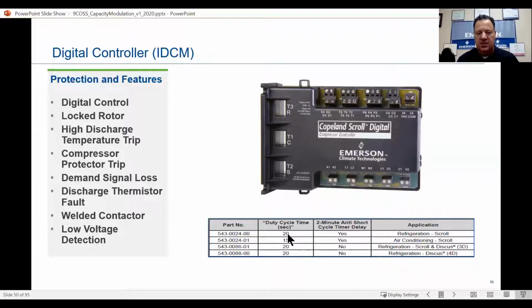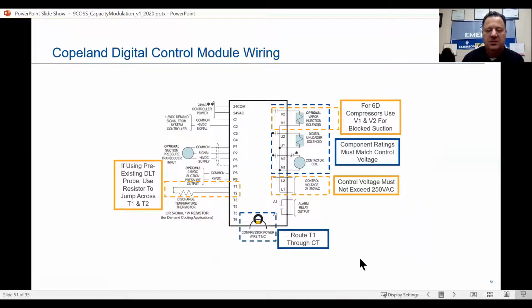Again, all the cycles are 20-second cycles, with the exception of the 15-second cycle that's for air conditioning scrolls. I'm not going to go through this whole wiring. I'll just pick out some things here. Again, low voltage on the left-hand side, high voltage on the right-hand side. We need to route T1 through the current transformer here, okay, because this is picking up the amps as it's coming through. As I talked about earlier, it's reading those. If you're using a pre-existing discharge line temperature probe, use the resistor to jump across T1 and T2.